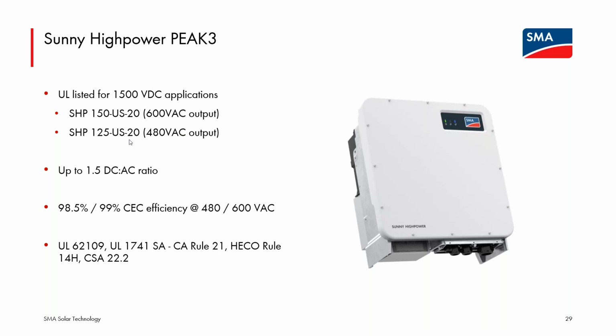The 125 kilowatt unit is a 480 volt 3-phase output, so similar connection to the CORE1 that we talked about. So this is very useful in the US for some building tie-in systems, so large co-located ground mount systems for a large facility. The 150 kilowatt unit is a 600 volt 3-phase AC device. Again, this is kind of in our utility scale portfolio. While it is a simple off-the-shelf string inverter, unlike our centrals that are very customized, this device is architected in a similar fashion. It is a single tracking channel input inverter, so we're assuming that there will be a large amount of space to have no concern with a large number of equal length, equal orientation strings coming to each and every PEAK3.